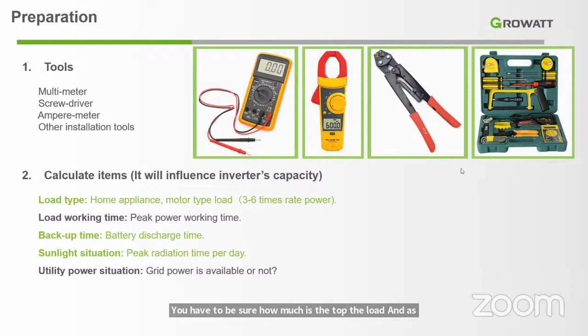The wiring must be really well fastened to avoid overheating and hot spots. Also watch the polarity -- you wouldn't believe how many calls we get because the PV polarity was reversed, negative where positive should be and vice versa. That can damage the inverter, so you have to be really careful. It's better to be safe beforehand -- just measure it with the multimeter so you're sure of the correct polarity before connecting.